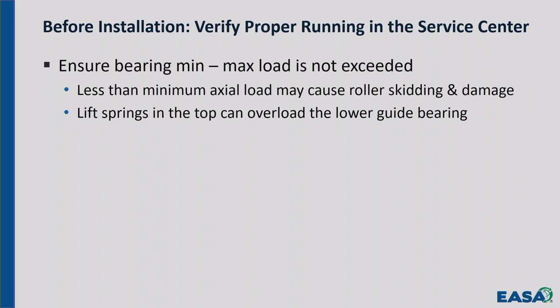Okay? You know about not running horizontal machines with a roller bearing on the drive end without any load on it, because the rollers will skip. You have the same problem with a vertical machine if you don't have sufficient vertical load. Okay? So that's a concern. With spherical roller bearings and multiple angular contact ball bearings, make sure that you have at least enough weight in the rotor to meet their minimum load.